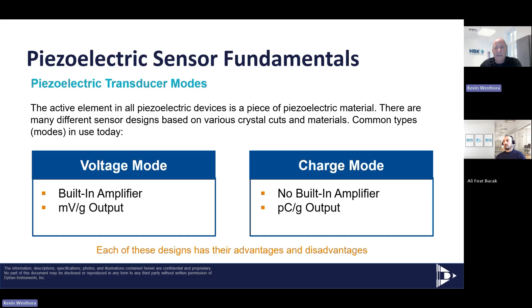Now that we know what a voltage mode accelerometer is, let's talk about some of the fundamentals. With a voltage mode sensor, an IEPE or ICP accelerometer, I can use many different materials. With a charge mode accelerometer, I'm limited in what material I can use because it's typically used for high temperature.